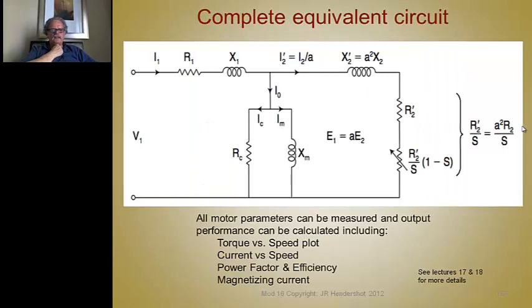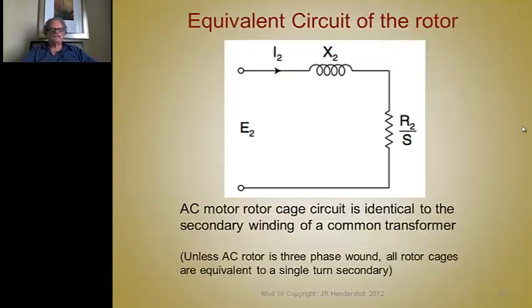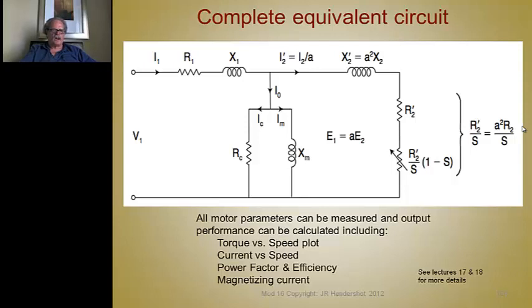This is the complete equivalent circuit, and all the motor parameters. All these motor parameters can be measured, and the performance of the motor can be calculated. You can take an existing motor and measure the equivalent circuit parameters, the voltage, the resistance, the inductance, the reactance, and from that you can calculate the current, the torque versus speed, power factor, efficiency, and magnetizing current. We're going to go over that later and go over how you measure those.